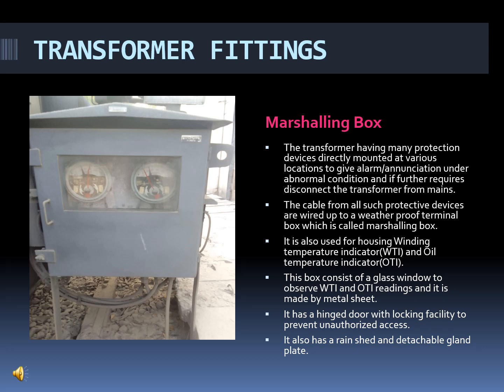It is also used for housing the winding temperature indicator as well as the oil temperature indicator. I have enclosed the image from my site. Here we can observe the winding temperature indicator on the left side and the oil temperature indicator on the right side.